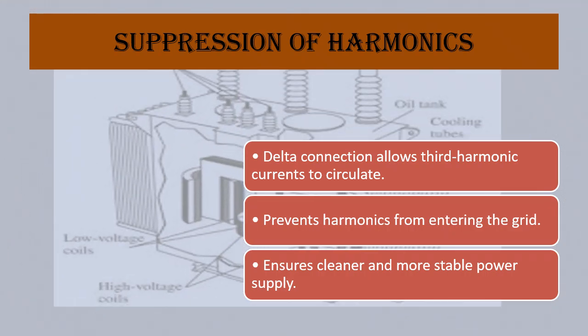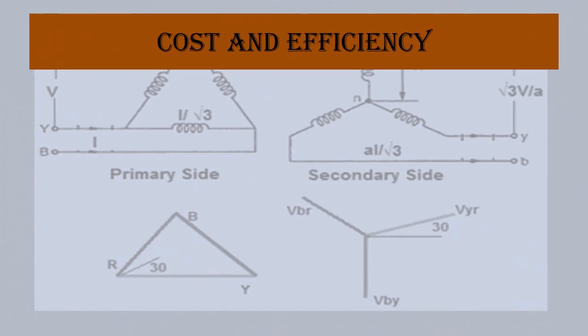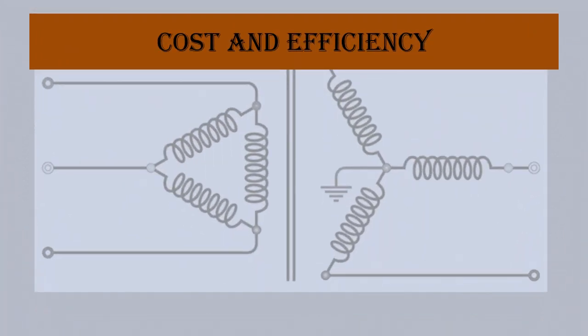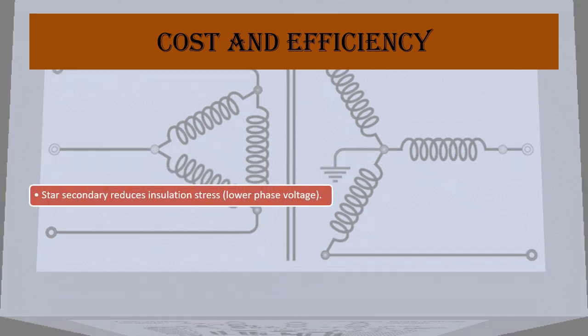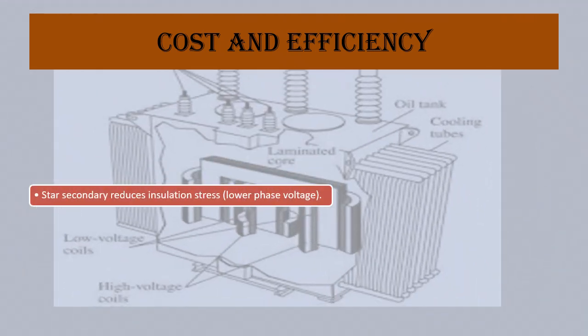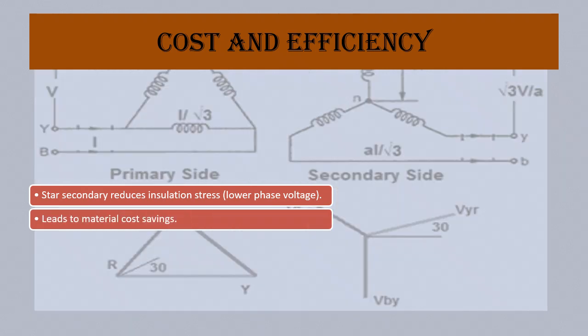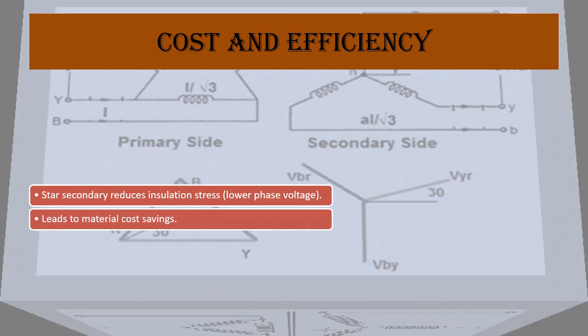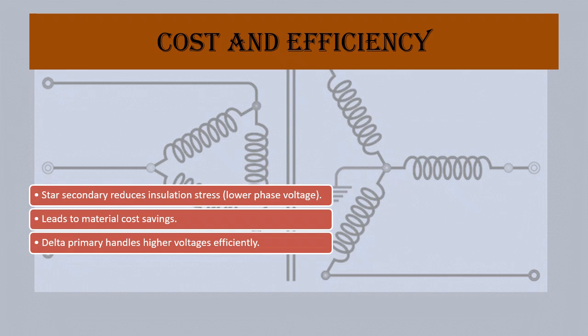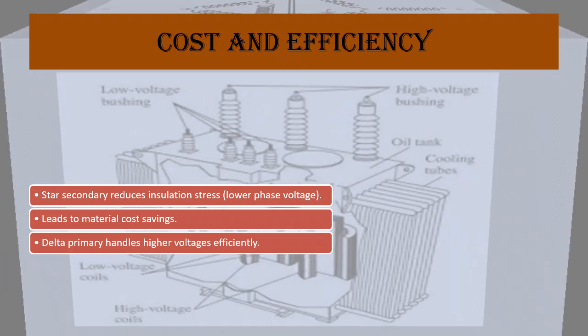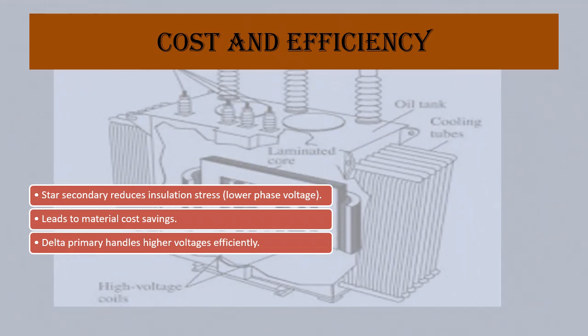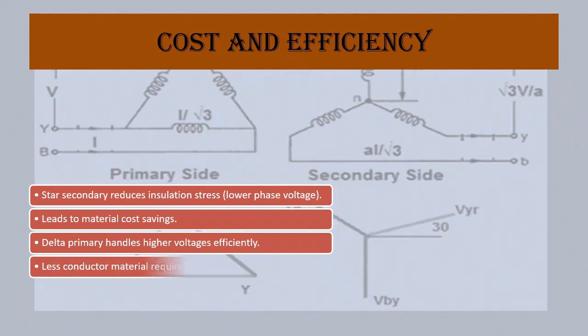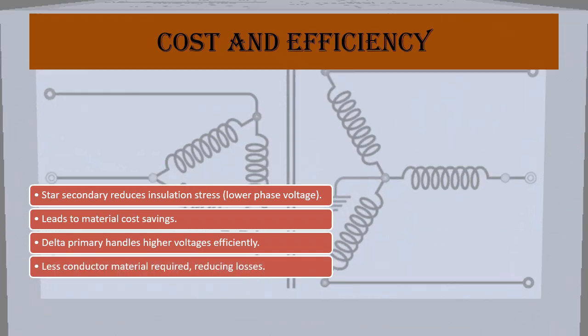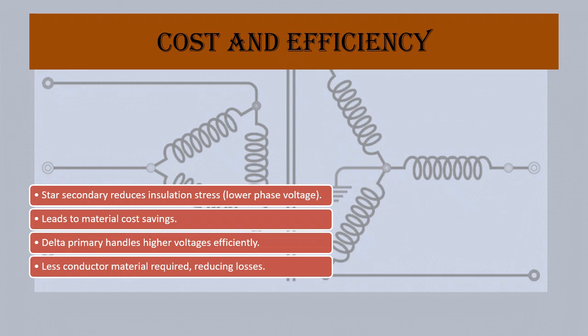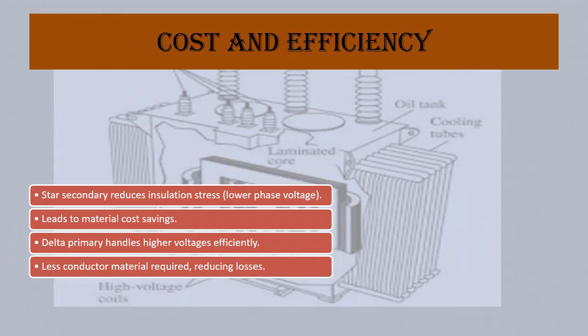Cost and efficiency. Finally, Delta-Star transformers are cost-effective and efficient. The star secondary reduces insulation requirements by lowering the phase voltage. This leads to savings in winding materials. Meanwhile, the delta primary can handle high voltages with reduced current, which minimizes resistive losses and reduces conductor material requirements. Together, these advantages make Delta-Star transformers a highly practical choice for distribution networks.